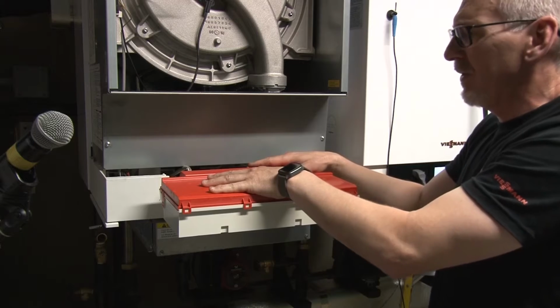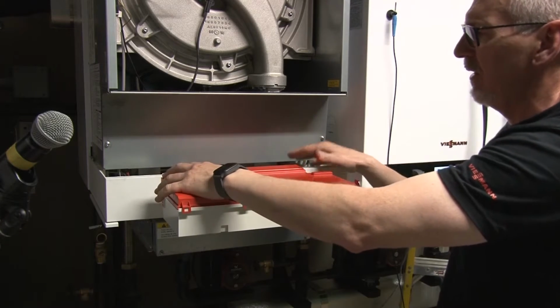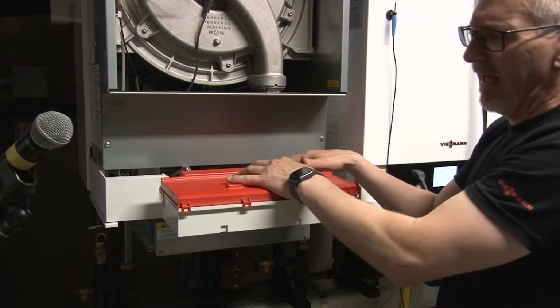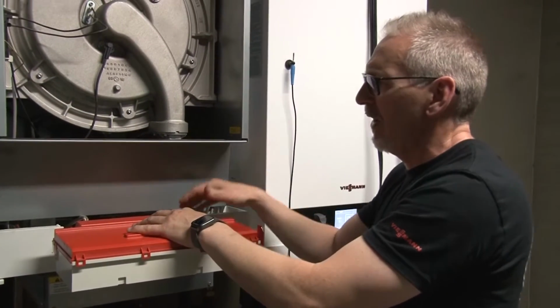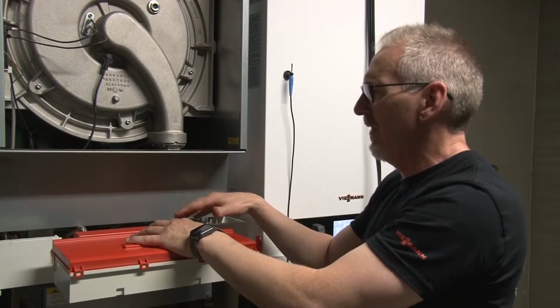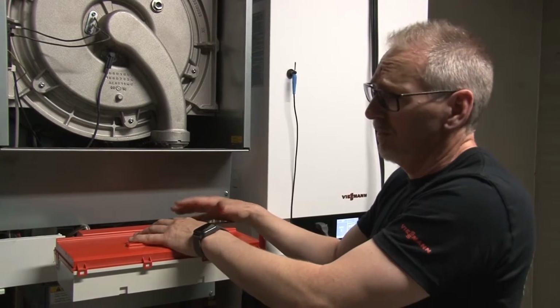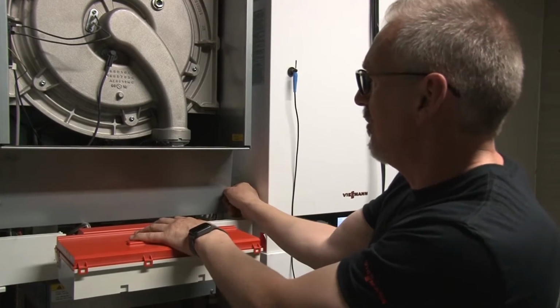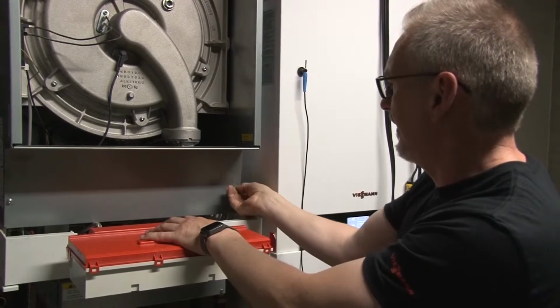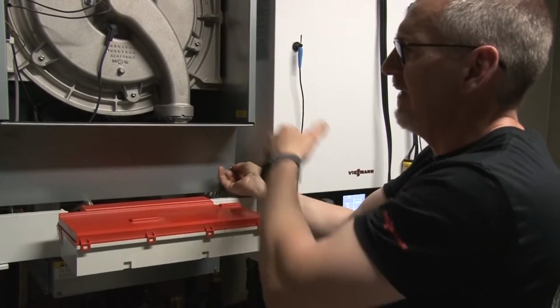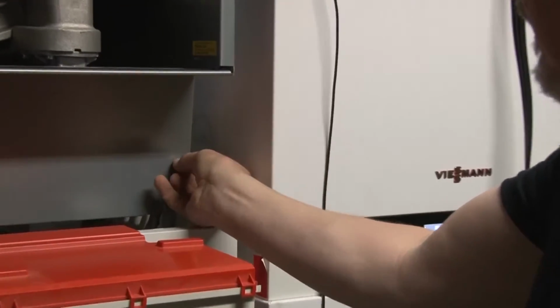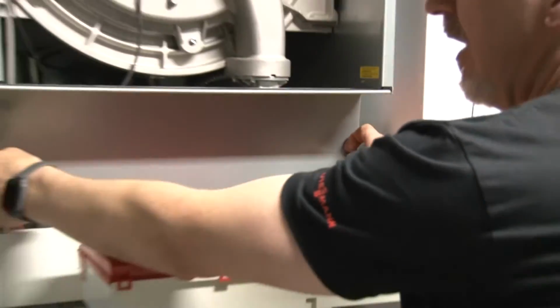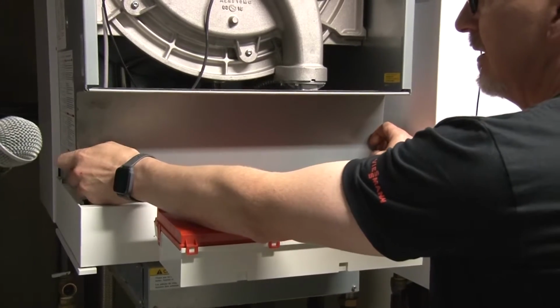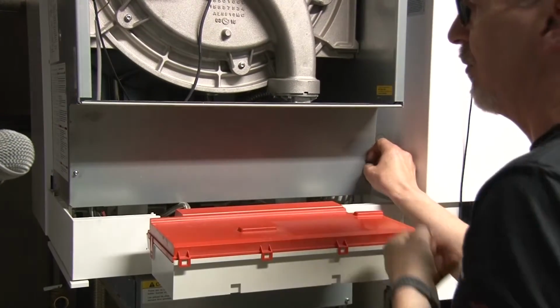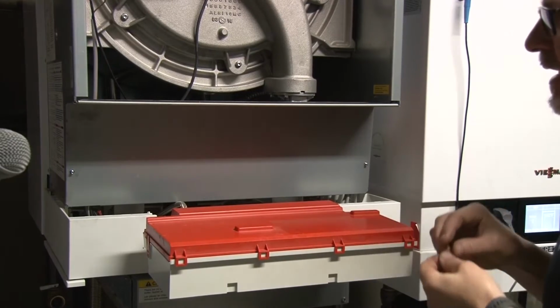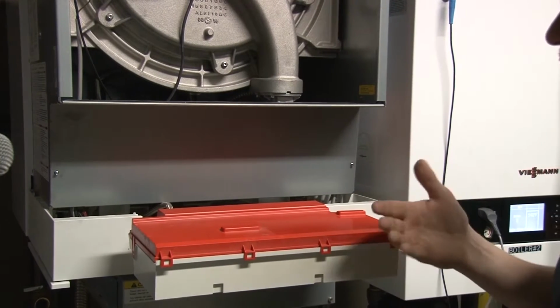So some guys will go to the extreme of, depending on what they're using for water for washing, they'll cover this with plastic or something like that, and we'll control the water here today fairly well, so to avoid that type of a problem. But control of water is important when you're doing service in these low mass boilers, because you're going to have that spray back and stuff like that. So just be thinking about how I'm going to clean that boiler and make sure you have the appropriate tools to do it.